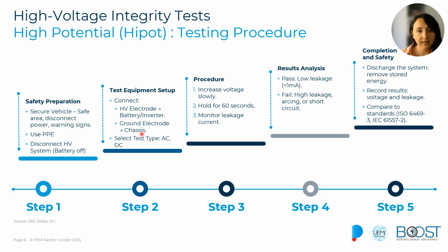In that step, the high voltage electrodes will be connected to the battery or the inverter, while the ground electrode is placed on the chassis of the vehicle. Also, we choose between doing an AC or DC test, depending on the standards that the manufacturer guidelines are using. And then we execute the test. The test requires us to slowly ramp up the voltage to the specific level and to hold it at the maximum level, often for about 60 seconds.